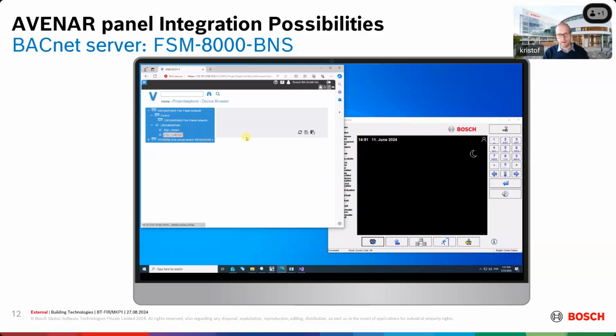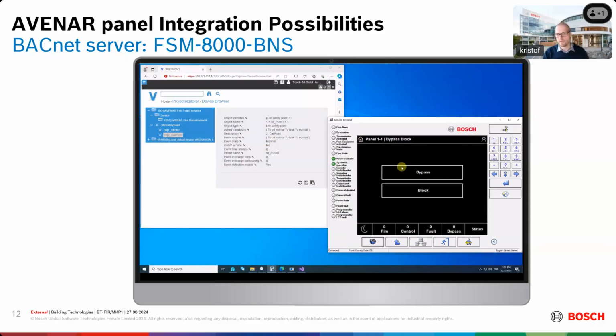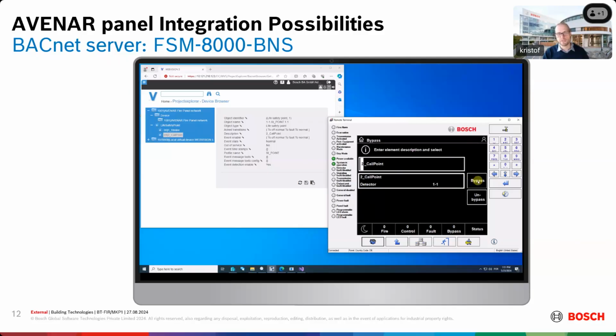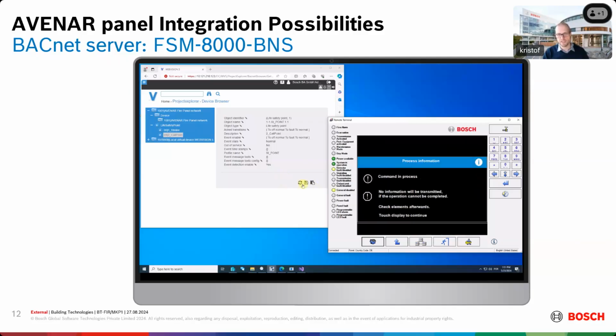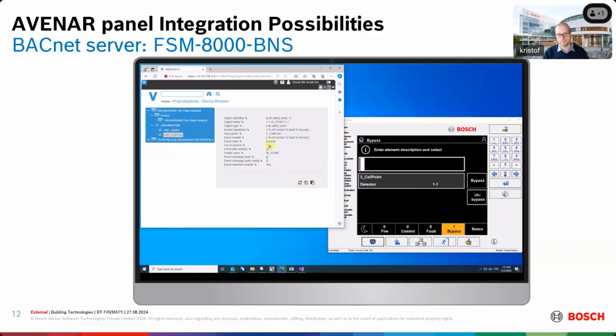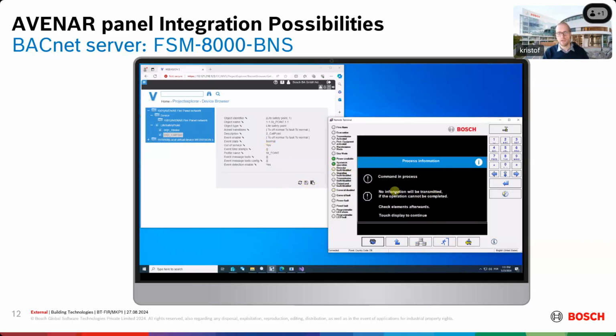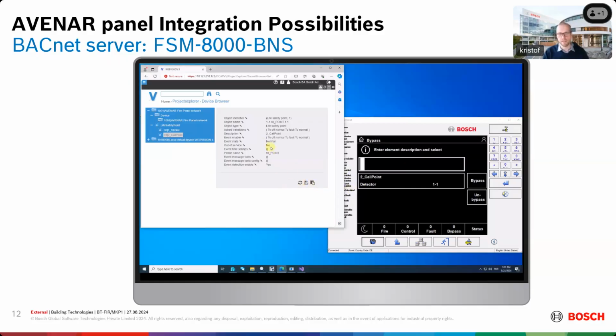Please also be aware that we have an out of service object. If you now bypass the manual call point, you will see that this out of service is changing from no to yes. That means now it is out of service. When it is no, it means if you put it back in service, it's again fully functional. So this is how BACnet really is standardized and how it is actually working as a plug-and-play solution.